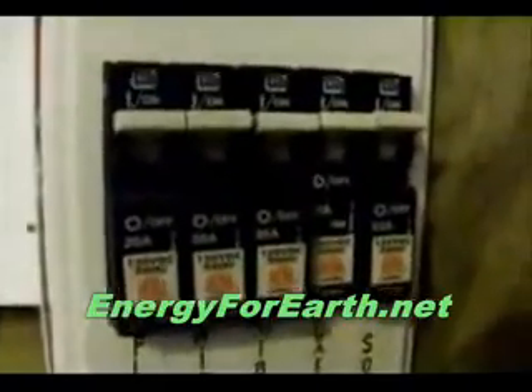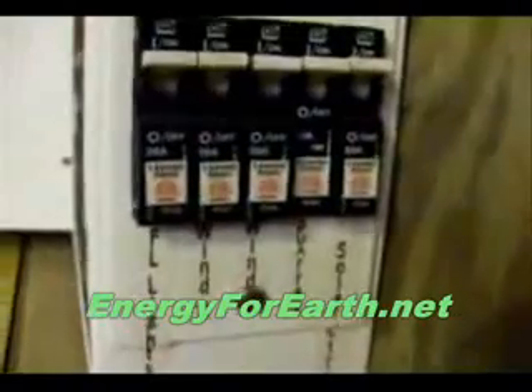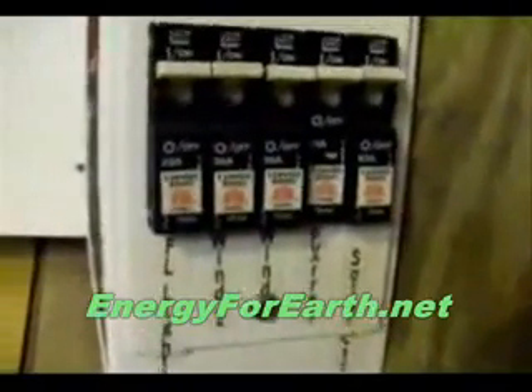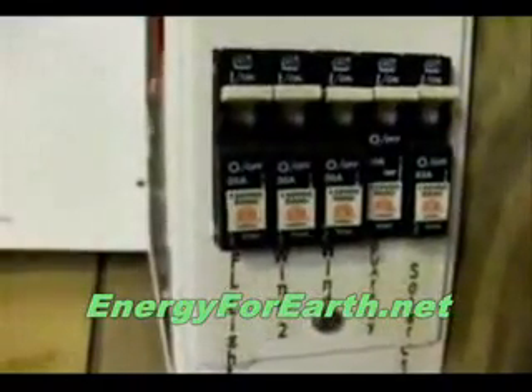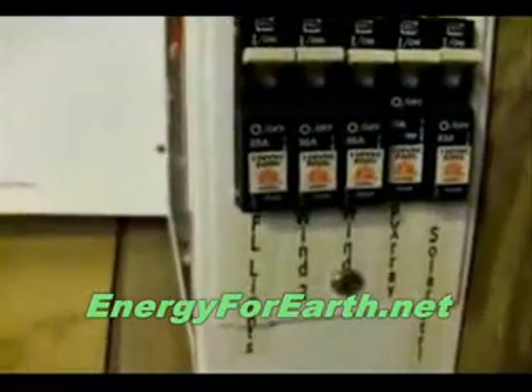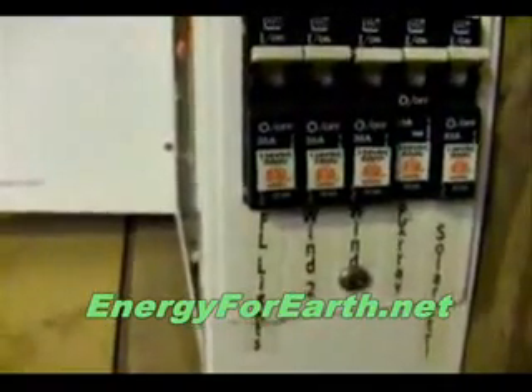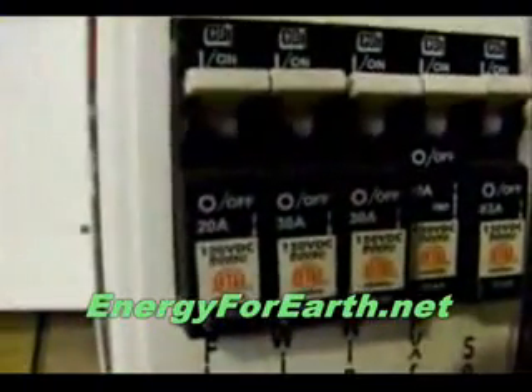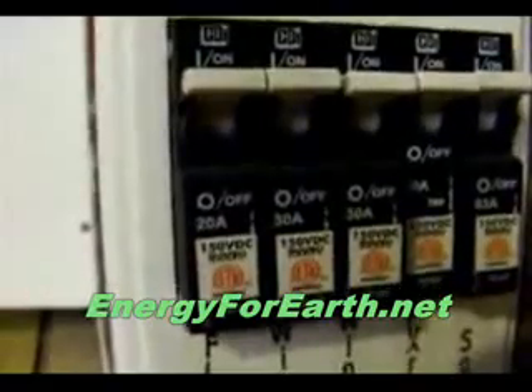Of course, these breakers are strictly for safety purposes and overcurrent protection. We have 5 breakers: one for our solar controller, one for our solar array or PV array, one each for wind generator 1 and wind generator 2, and I also have some 12 volt fluorescent lamps running downstairs. You can see the various amperages, anywhere from 20 to 63 amps, and of course our main is 250 amps.